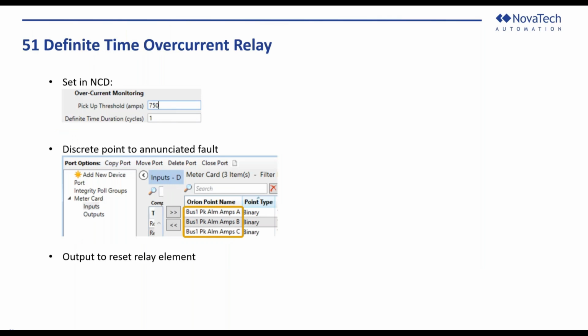We talked about the definite time over current element. This is a 51 definite time. It's set in NCD. You can set your pickup threshold in amps and the duration. There is some hysteresis built into that, 3%, so that after you pick up, if you would drop slightly, you don't keep picking up and dropping out. The annunciation of a pickup is in these points. These are inputs that you can read from the meter card, and you can see the binary input there indicating that you picked up on phase A, B, and C. There also is an output to reset the relay element.